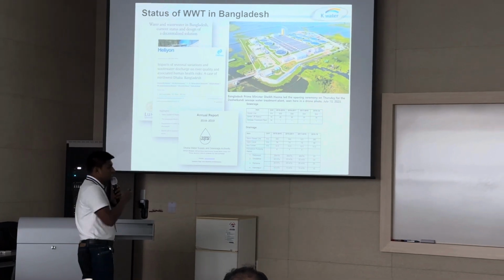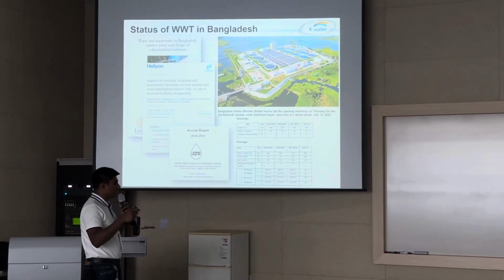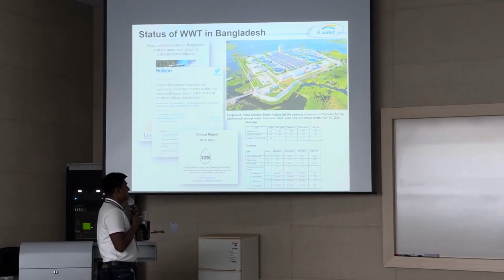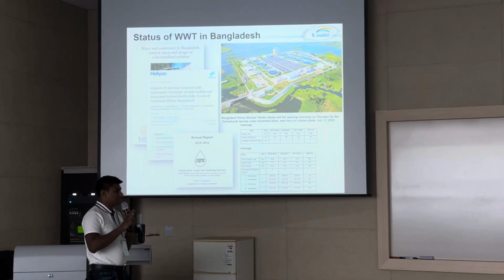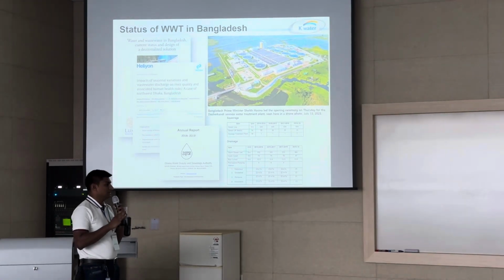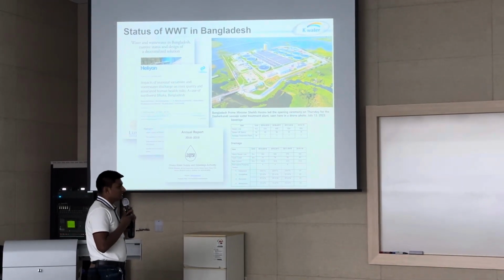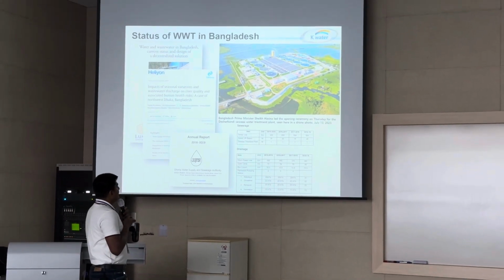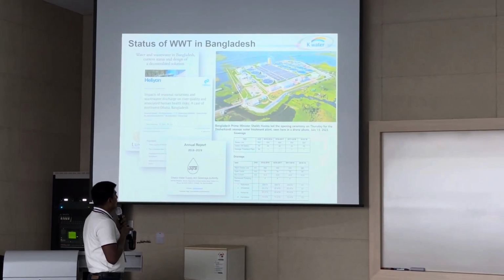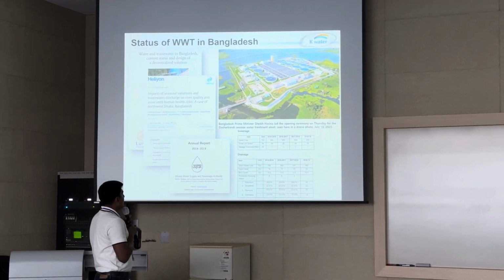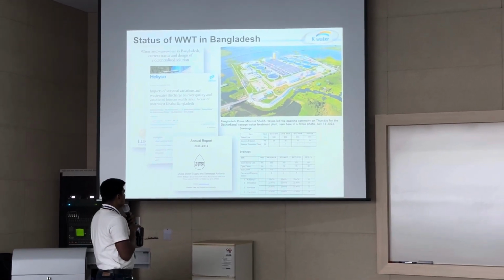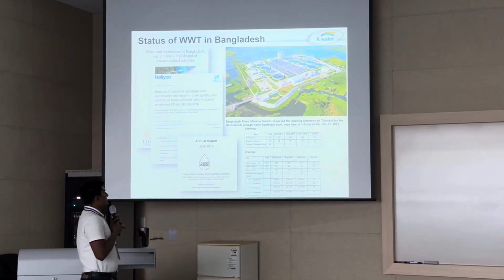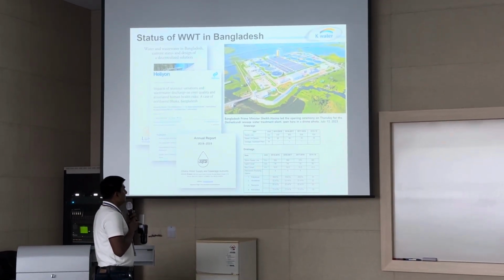Then we have, as you demonstrated, the AAO or anaerobic anoxic oxic A2O system, which is capable of removing the three basic nutrients, that is carbon, nitrogen and phosphorus. That is the A2O process. We have incorporated the A2O process, and then it goes into the secondary sedimentation tank. The whole process, the A2O and the secondary sedimentation, is the biological process.